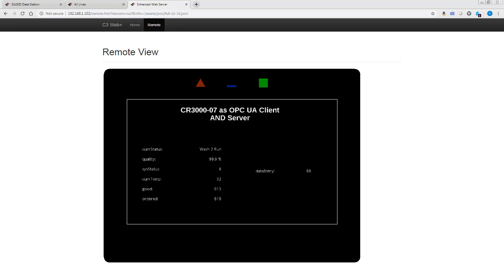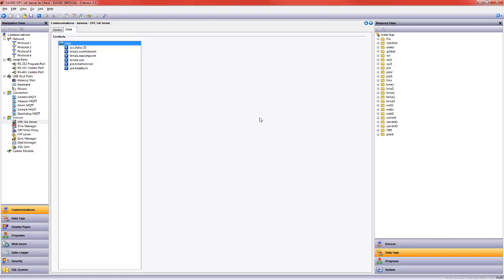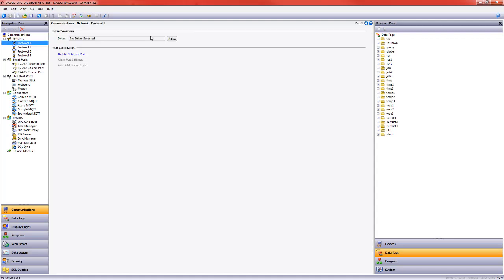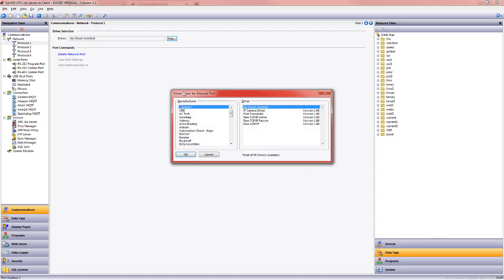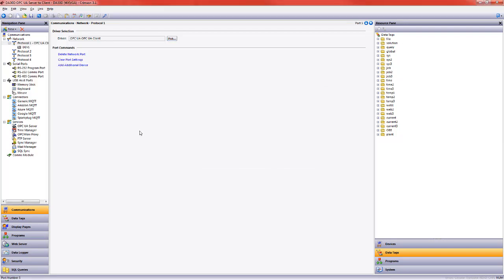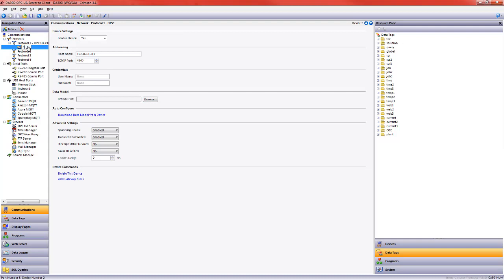I want to set that up as a client. So I'm going to come over here, go to network, protocol. I'm going to choose my OPC UA client. I just typed OP to get there very quickly. I'm going to make a note that this is a CR3000-07 in my system. And I need to tell my data station the IP address of my OPC UA server, which in this case is my CR 3000. I hit enter.